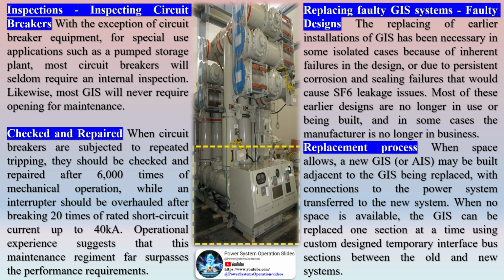Inspecting circuit breakers. With the exception of circuit breaker equipment for special use applications such as a pumped storage plant, most circuit breakers will seldom require an internal inspection. Likewise, most GIS will never require opening for maintenance. When circuit breakers are subjected to repeated tripping, they should be checked and repaired after 6,000 times of mechanical operation, while an interrupter should be overhauled after breaking 20 times of rated short circuit current up to 40 kA. Operational experience suggests that this maintenance regimen far surpasses the performance requirements.